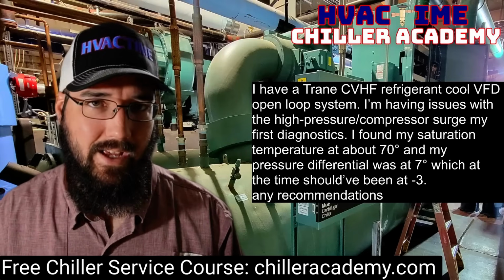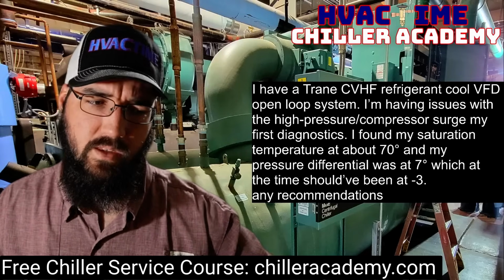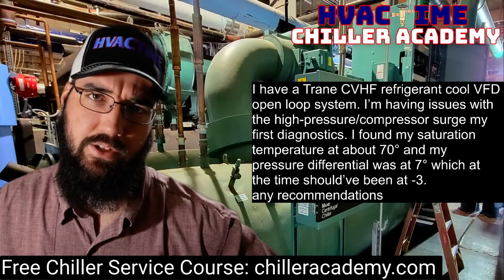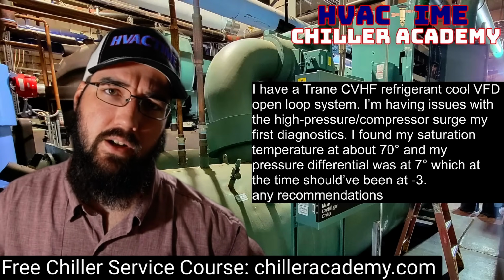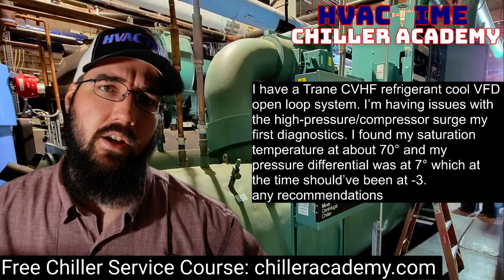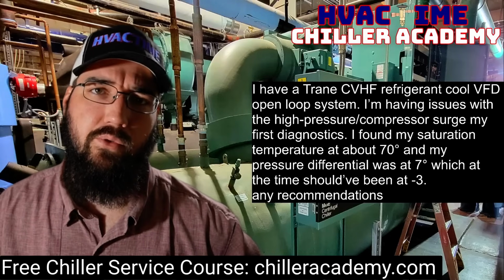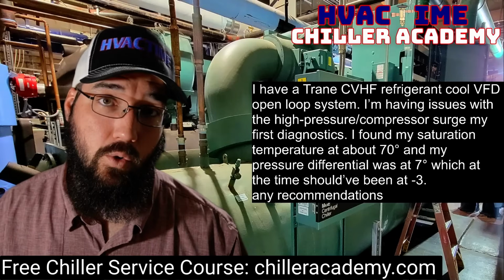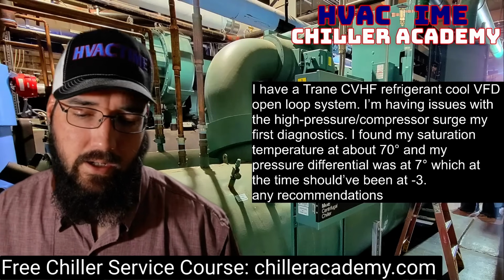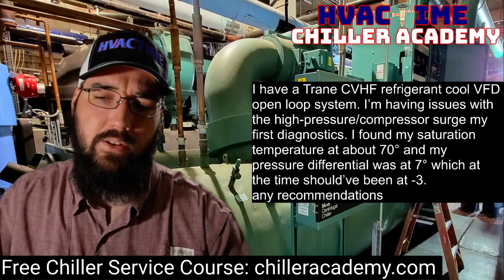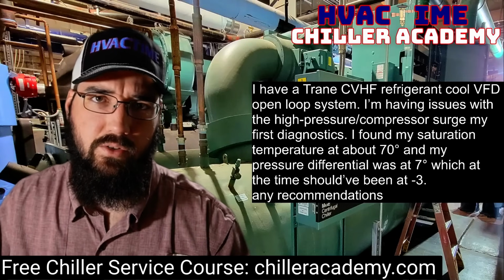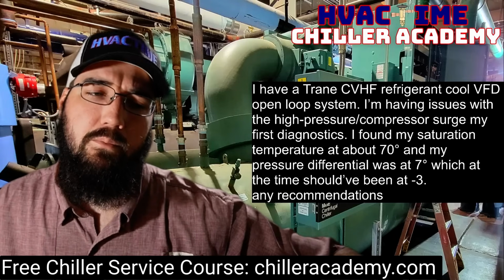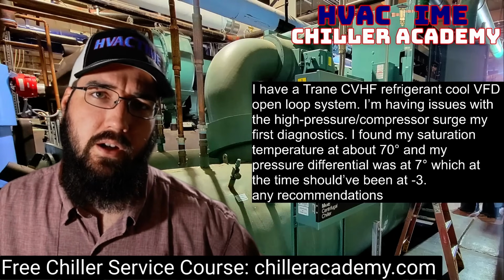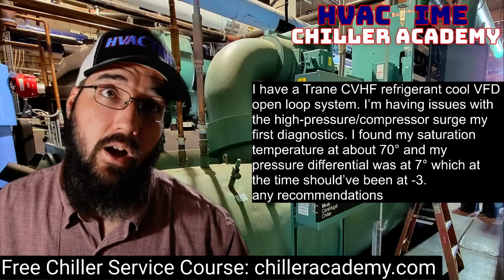So is that clear? Are the valves clear? What I mean by valves is there's an isolation valve on the liquid drain valve, and there's an isolation valve on the hot gas intake valve for the purge system. Are those actually open? Are they working? That'd be another thing I'd want to confirm. So just overall, is the purge system working? And I would go through a troubleshooting process until I felt confident that it was.